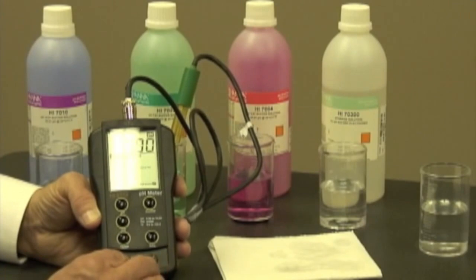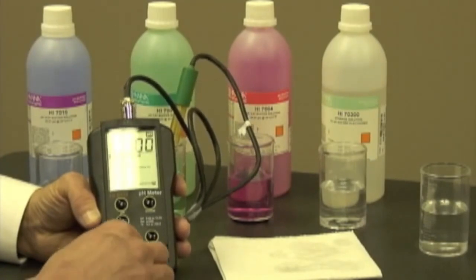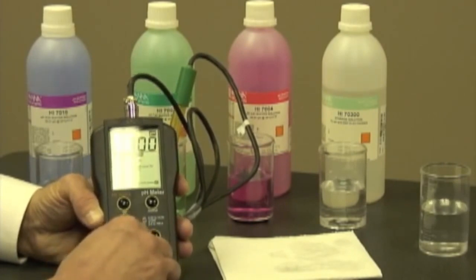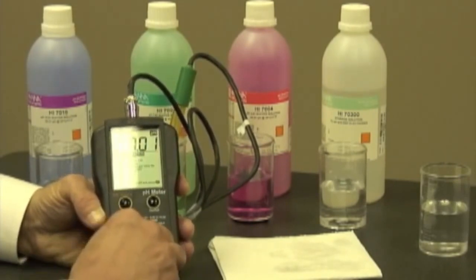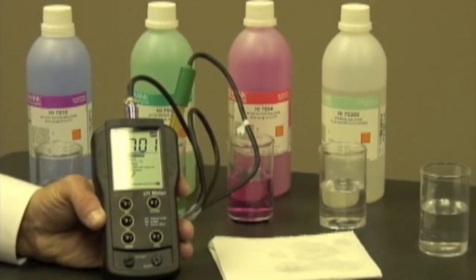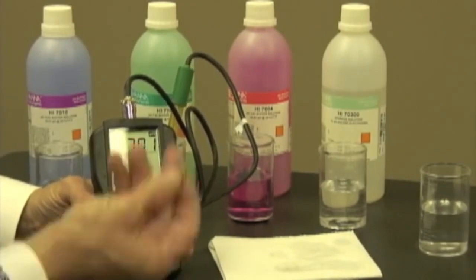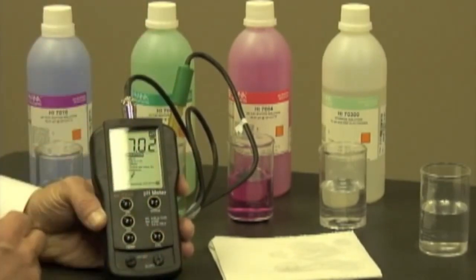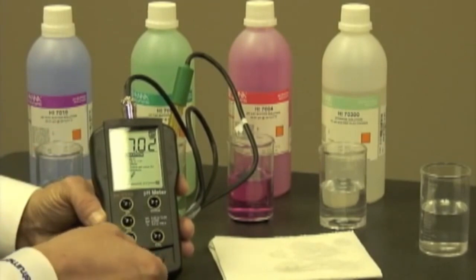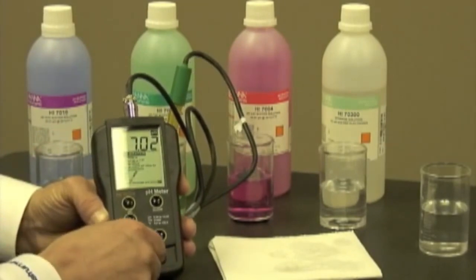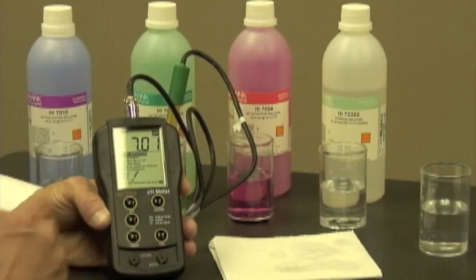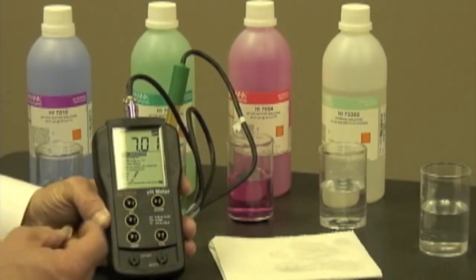Now, the meter says 6.99. So what I want to do is adjust the offset to 7.01. So I'm going to turn the knob. Now I can turn the knob either with a screwdriver or a coin. So I've gotten it to 7.01. Now it's going back to 7.02. So I'm going to give it a little tweak and we're at 7.01.